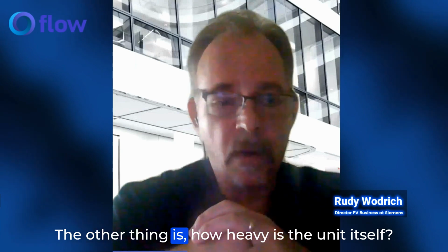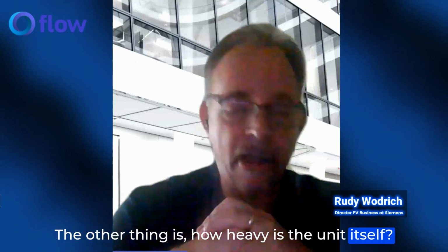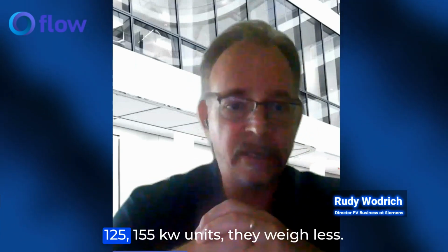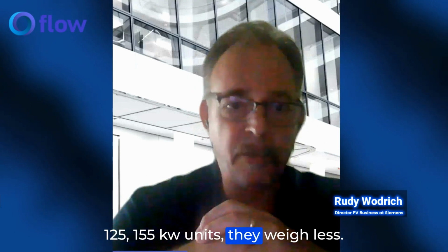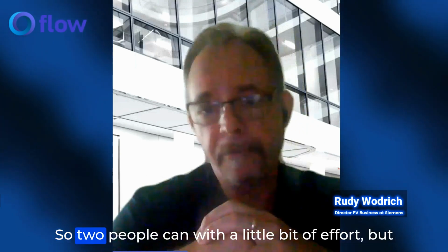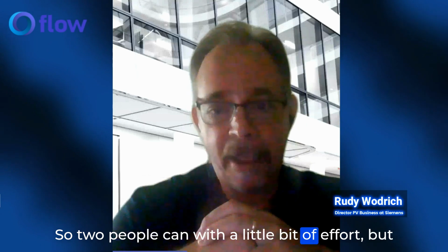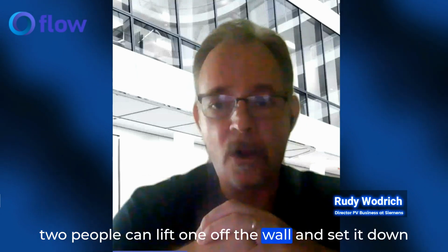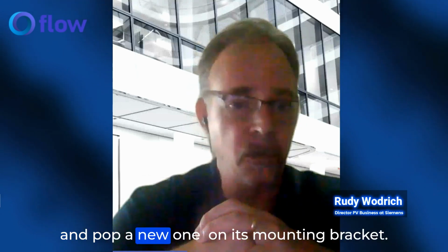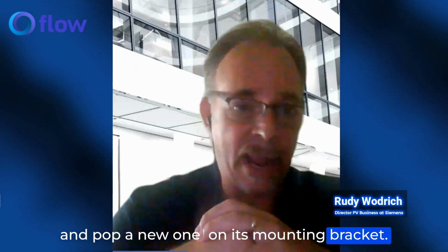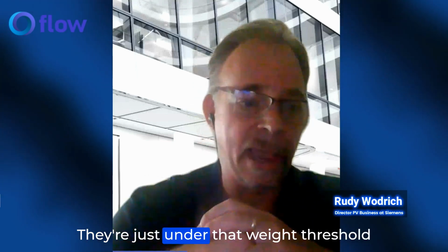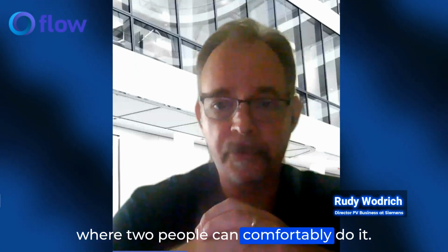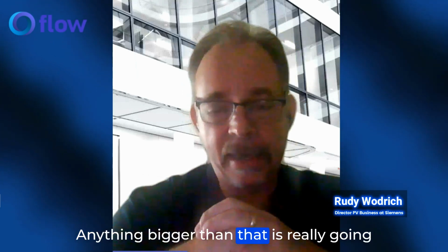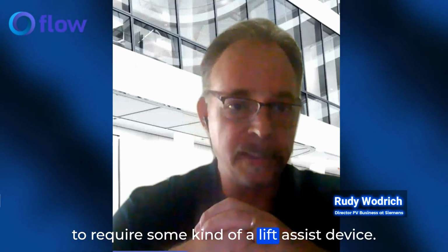The other thing is how heavy is the unit itself. The units we deploy, these 125, 155 kW units, weigh less than 80 kilograms, so 2 people can, with a little effort, lift one off the wall and set it down and pop a new one onto its mounting bracket. They're just under the weight threshold where two people can comfortably do it. Anything bigger than that really requires some kind of a lift assist device.